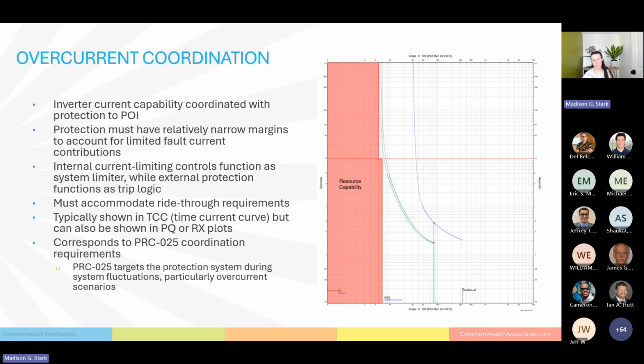So where that comes in is the inverter internal controls have to be coordinated with the system protection, which is the same thing that you see for PRC 19, because you want your system capabilities, which are tied to those internal controls, coordinated with the system protection capabilities. So a lot of overlap there for the inverters.